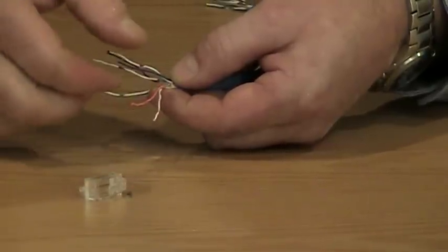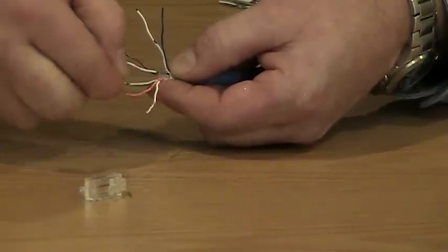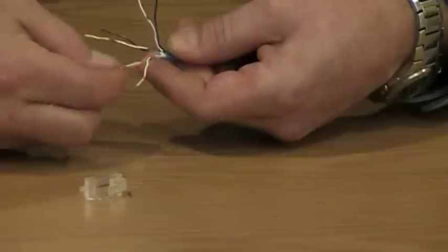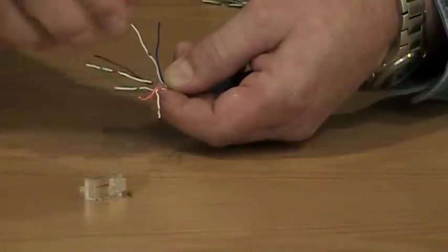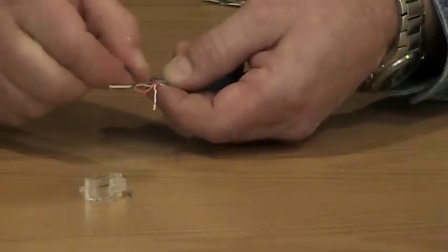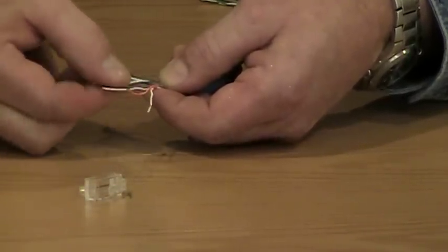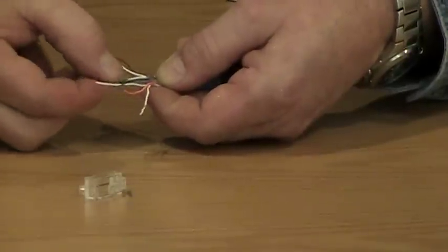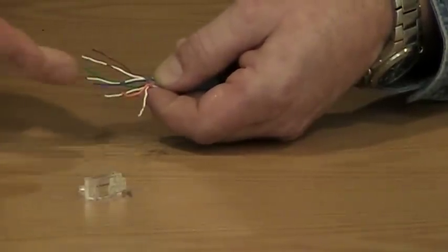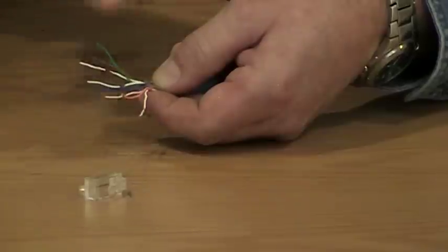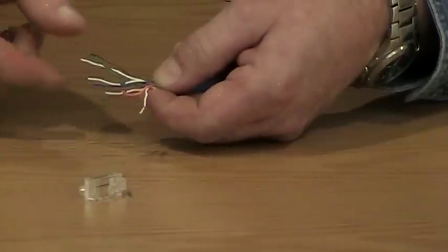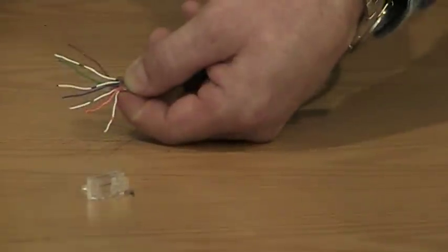So we're going to go left to right: white orange, orange, the third conductor in that sequence is white green and I'm going to bring that to the bottom so it's in that slot in the bottom. Now the blue and white blue come down to the top, and the sequence goes white orange, then orange, white green, then blue, white blue, then green, and the green is laying in that slot in the bottom, and then white brown and brown. That's the proper sequence for us.